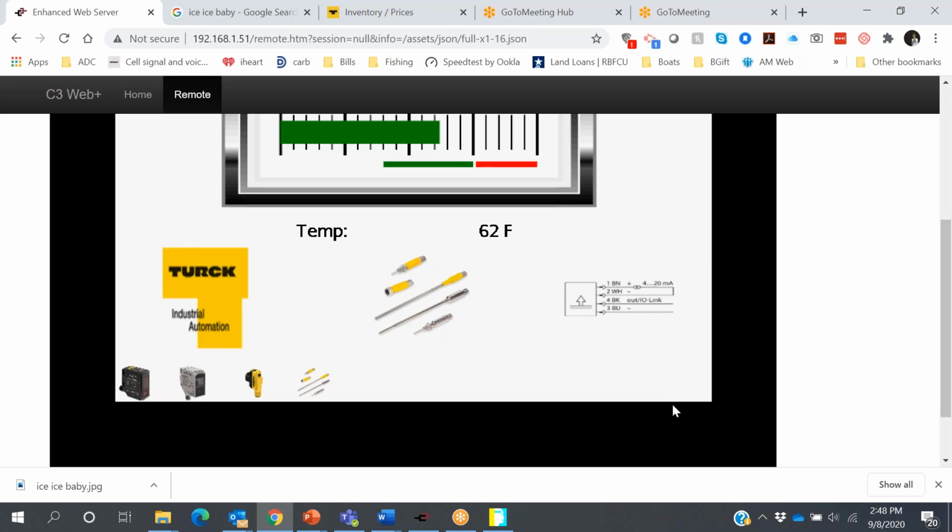Now when it comes up, you won't see it do anything special. It's just going to come up and start reading in milliamps. And now when we don't have any signal at all, you see those 3 LEDs are gone. Those LEDs are an indicator of what mode it's in. So just by changing the port it's on, it immediately got a new configuration. You could have the same spare with factory defaults and confidently put it into different applications. Sorry I forgot that, but I thought it was an important thing to talk about.